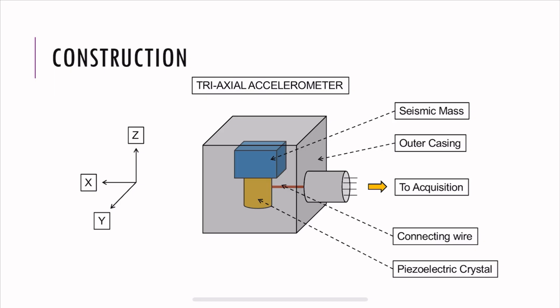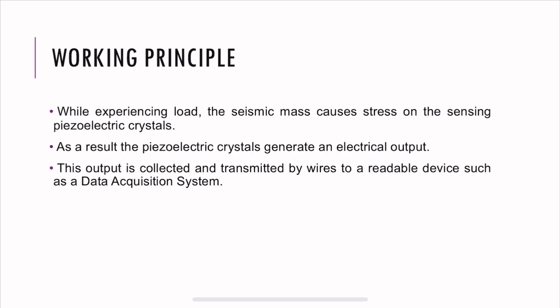When you're actually measuring, the seismic mass puts the load on these crystals, which produce an electrical charge, and which travels to your data acquisition system. There are a lot of conversions that take place, and finally you see the accelerations there.